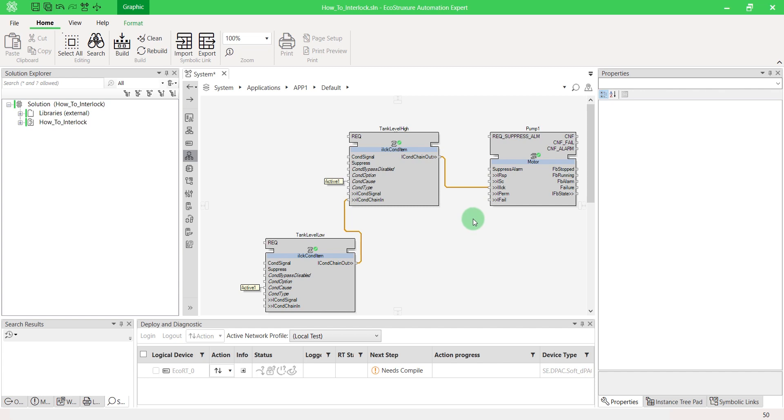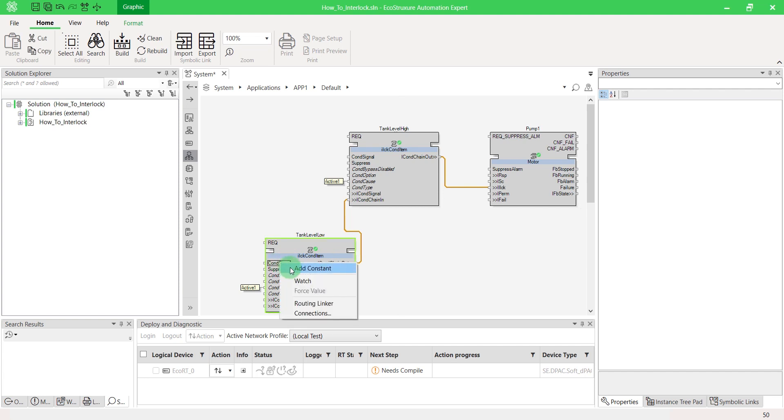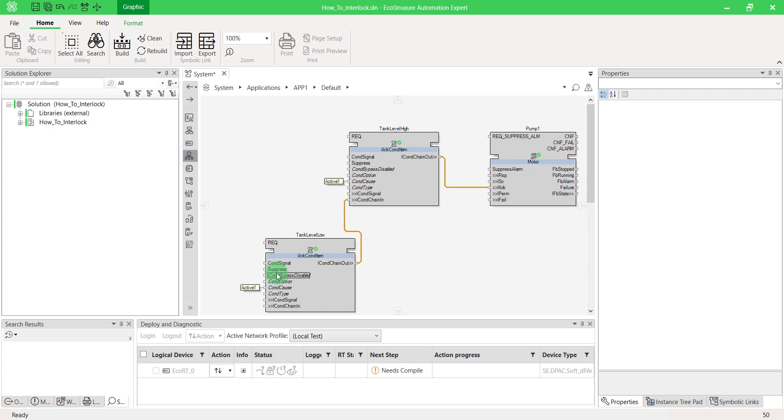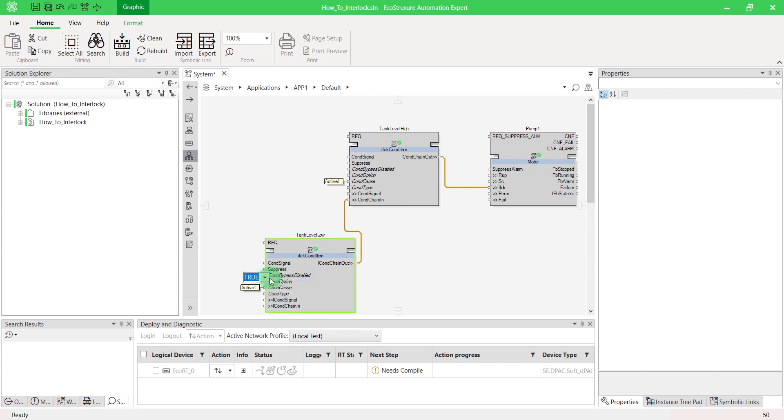Let's configure interlock blocks. Cond signal is a boolean that corresponds to the condition state. It can even be brought through an adapter. In case both are connected, the adapter has priority on the simple boolean. Suppress allows you to bypass the interlock. Cond bypass disables the possibility to set the bypass from the HMI faceplate.